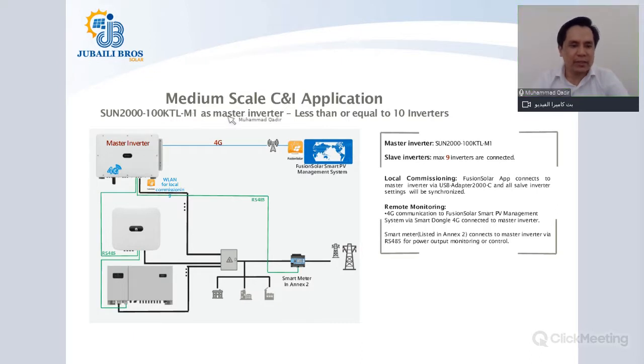And again, a medium scale when you are using a 100 KTL inverter as master inverter. In this scenario, the number of slave inverters will be 9, and you have the only option of the 4G dongle, or you can also have the Smart Logger. But in this scenario, you have the 4G dongle, so remote monitoring can happen only through 4G communication. Local commissioning will happen through FusionSolar using the USB adapter which comes with the inverter.